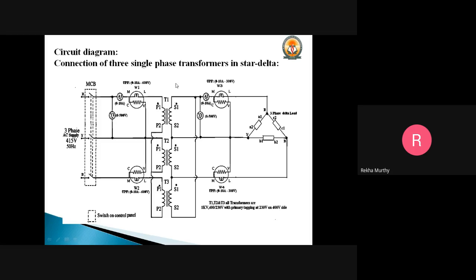So in delta fashion, on the delta side you will find that this is S1 of the first transformer, this will have an S2, and the next will be S1. This is how it is shorted, and S2 comes here. Similarly, the next phase S1 is coming here, and S2 is coming here. So this is how we need to make sure we complete this loop.